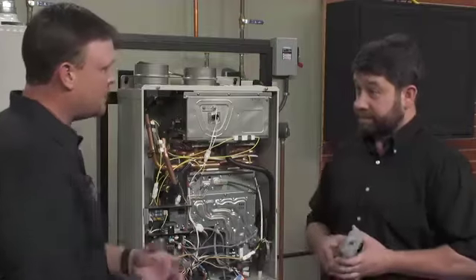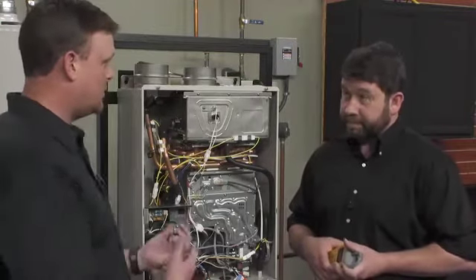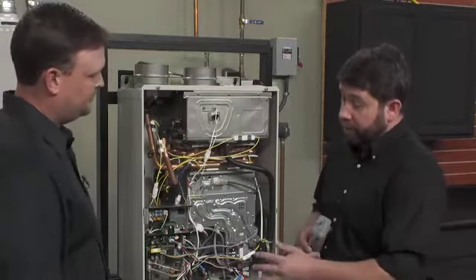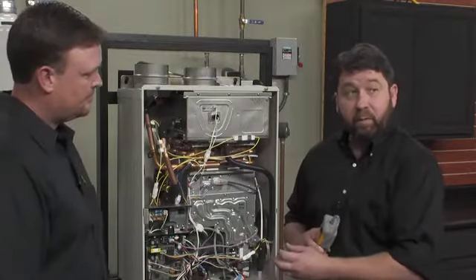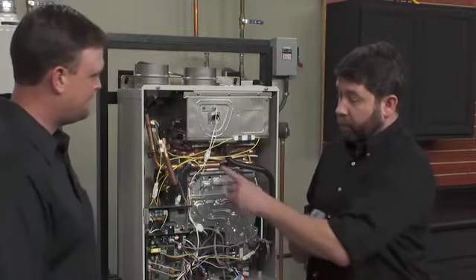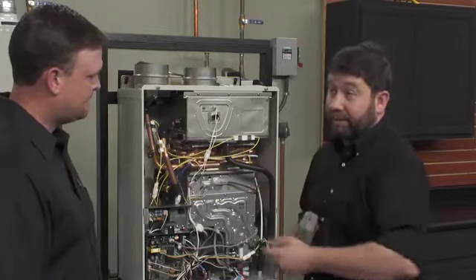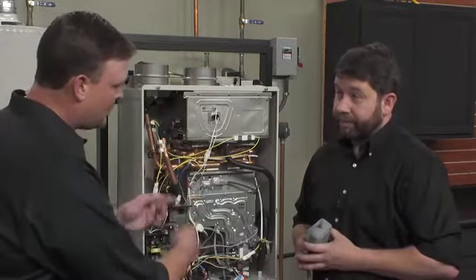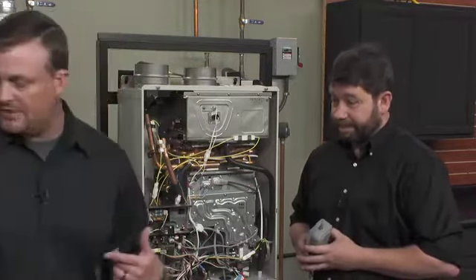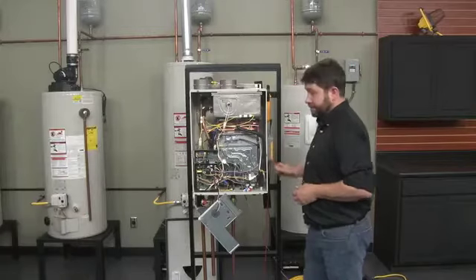So we turn it off, turn it back on. Now we don't hear the clunks. What do we do? If we don't hear the clunks, it's going to go to a 711 error code. Okay. So one of these two safeties has opened up. The safeties are actually wired into the gas valve, and I've got a gas valve here. I'll show you what we're talking about.